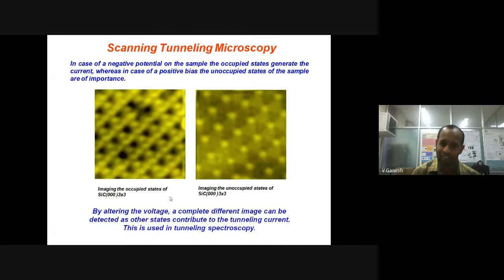You need to work on that aspect by scaling up. For example, if you initially scan 10 nanometers by 10 nanometers, and you double the area of scan, the structural features should also double. Instead of getting double structural features, if you get triple or four times, that suggests it is an artifact and not a real representation of your sample substrate.